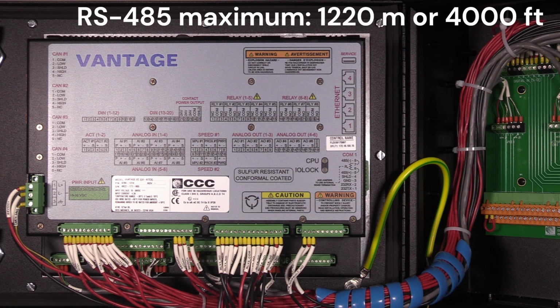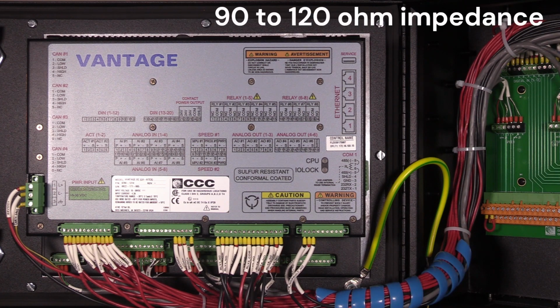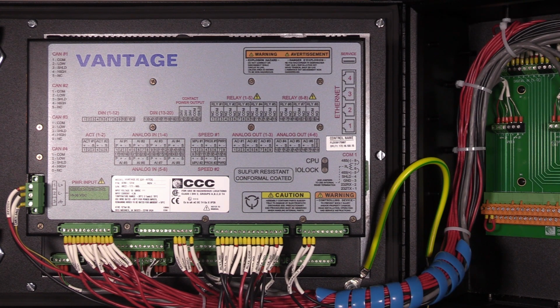RS-485 networks require termination at both ends with approximately 90 ohm to 120 ohm impedance that matches the characteristic impedance of the cable used. The same cable used for CAN connections is recommended for serial connections. Serial connections should be wired according to the chart on the back of the controller.